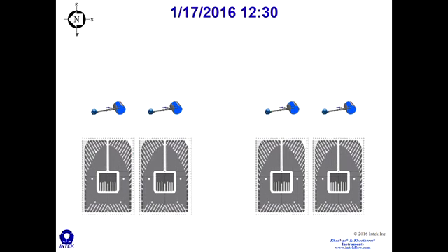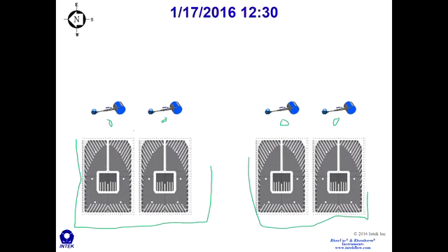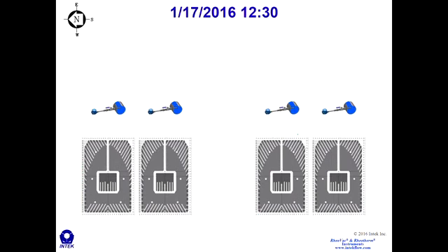And so this unit was in India, and so we shipped some instruments over. We had some engineers go over, and we installed RheoVacs at each offtake from each one of these bundles. So this is the condenser. There's two shells here, an alpha shell and a bravo shell. And each bundle has an offtake here, here, here, and here. They combine and they go to a single set of vacuum pumps, and we had RheoVacs installed in each one of these offtakes.